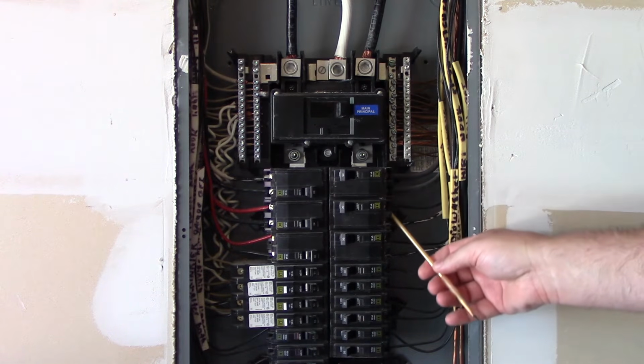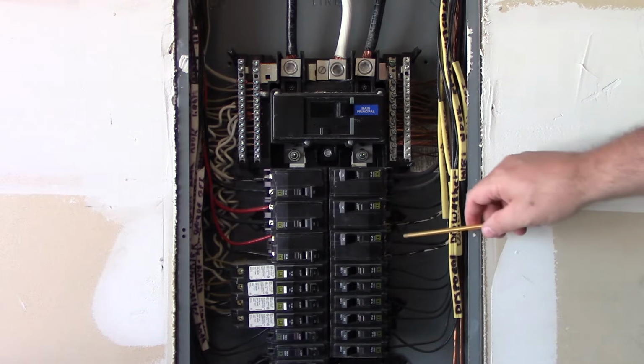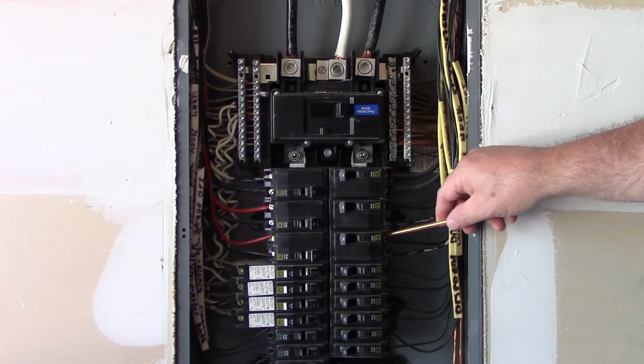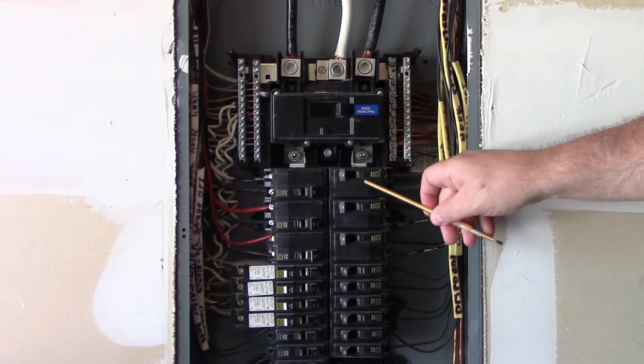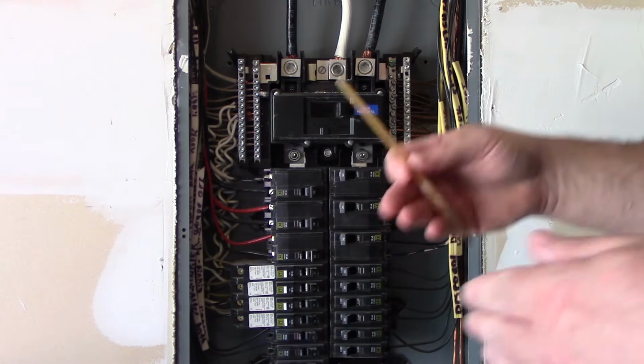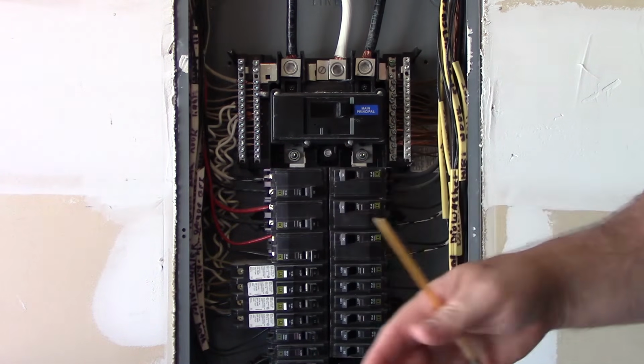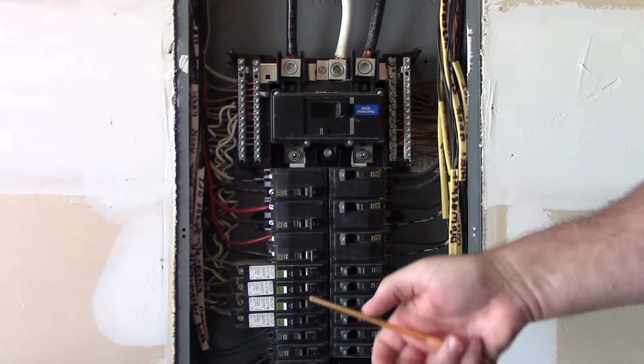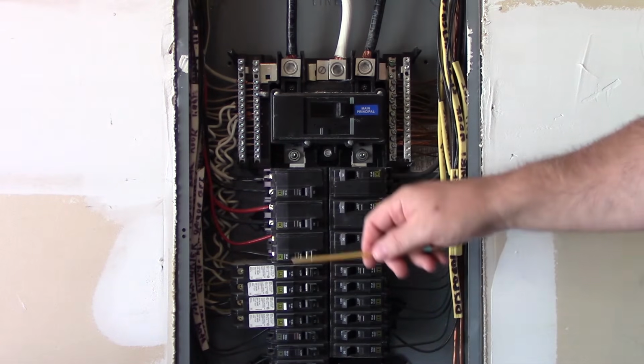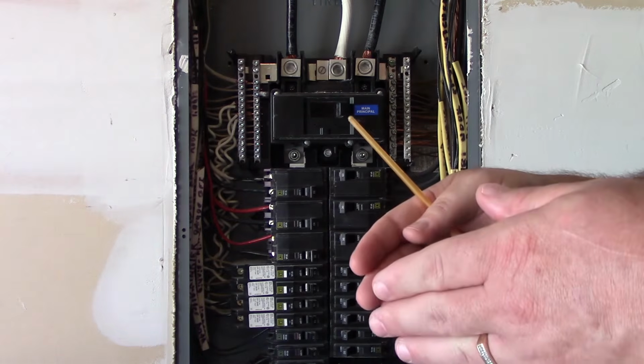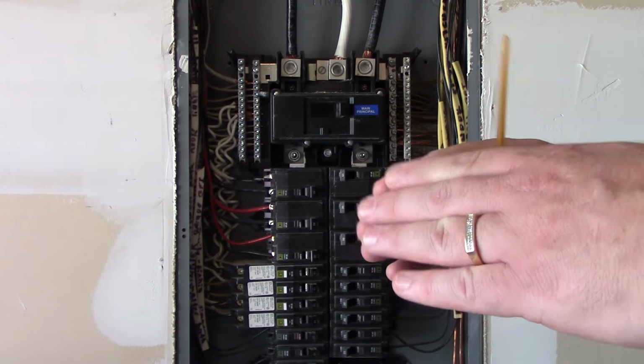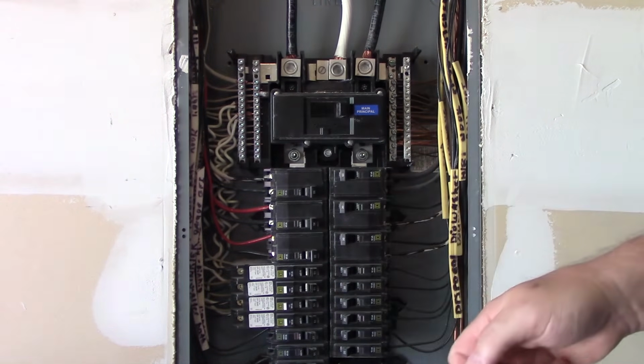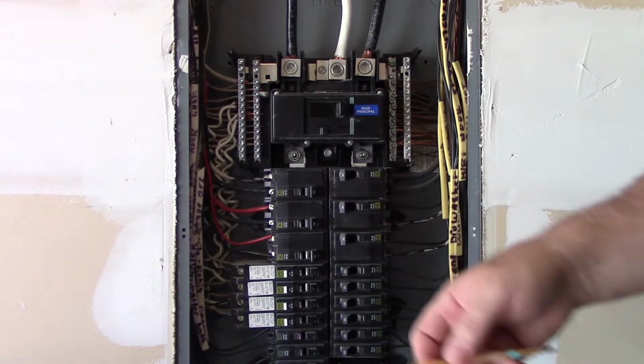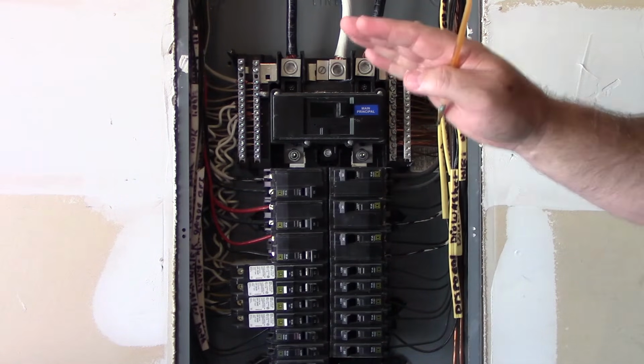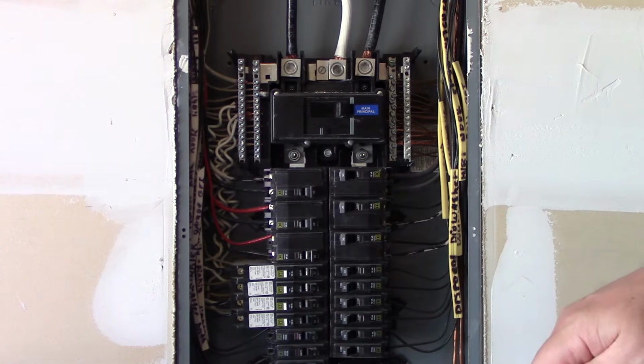We're also going to look at all of these terminations. If we have two conductors on a terminal, that's called a double tap. We then have to look and see whether or not this breaker is designed to handle two conductors. Not all breakers are. I know that in the QO brand, the 15 and 20, and they do make a double pole 30, will accept two conductors on what's called a saddleback type of termination. But you won't find that in the 40s or the 50s or even in the 60s. It's going to be on the lower ampacity rated overcurrent protective devices.